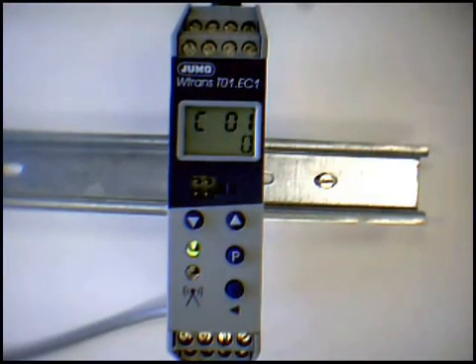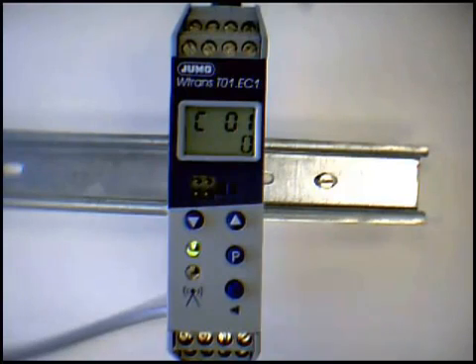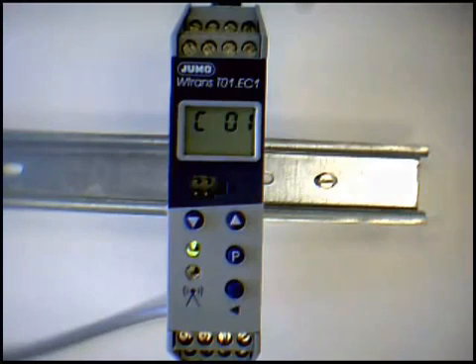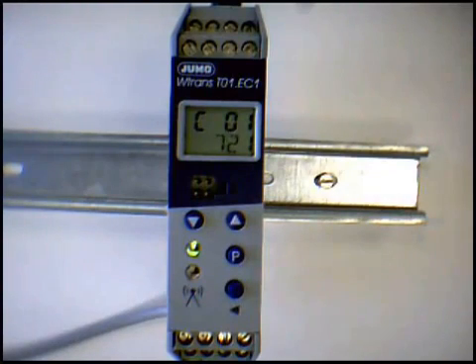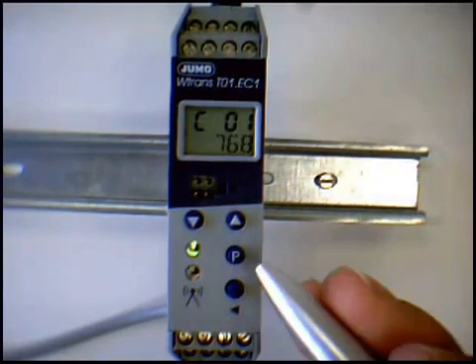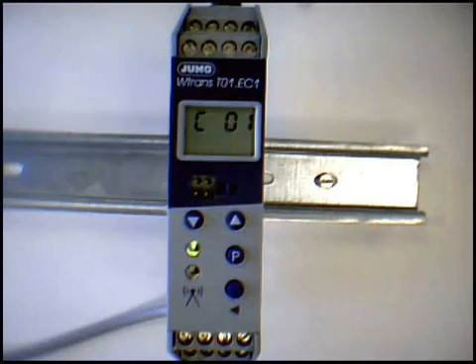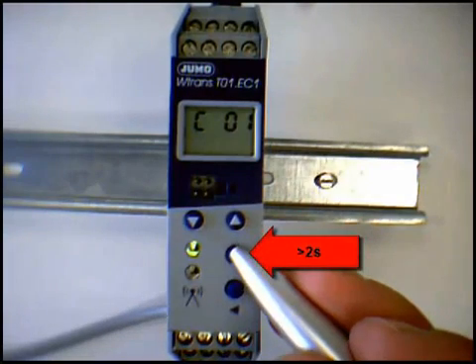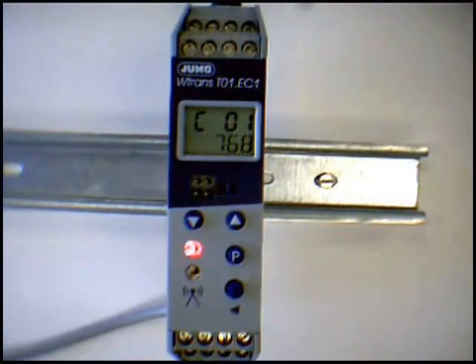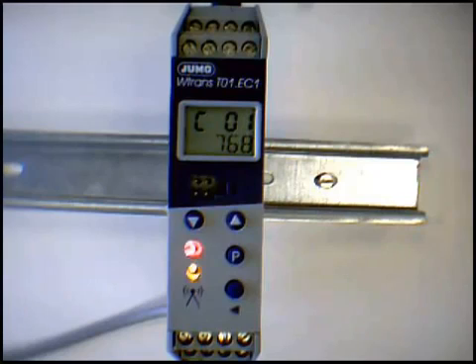The first channel is displayed. Please select P and you reach the link list. The numbers which appear now are the IDs, which are laser printed on the protection tubes. We select the ID 768. The measuring value of the relevant transmitter is now displayed in channel number 1.